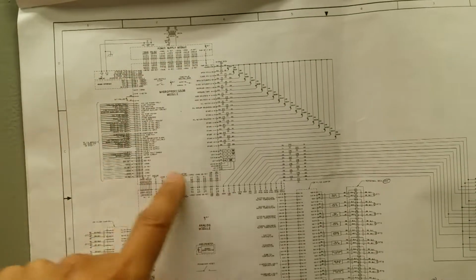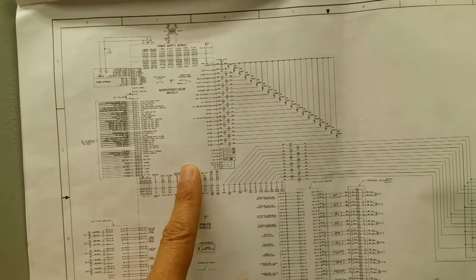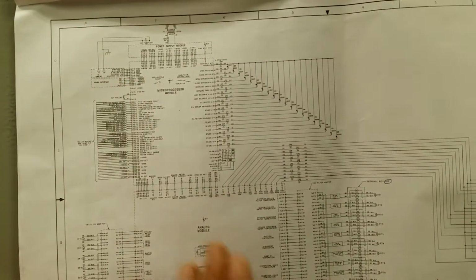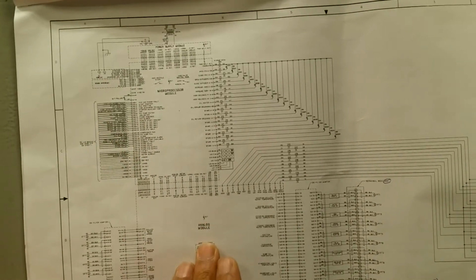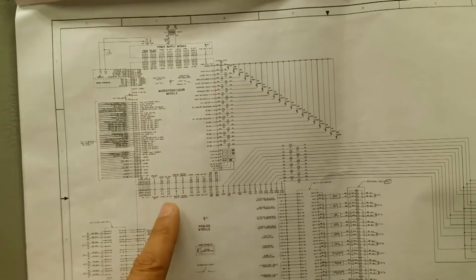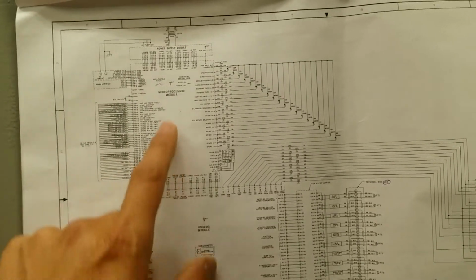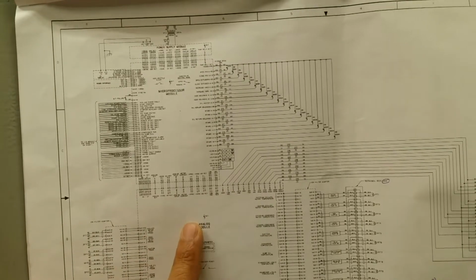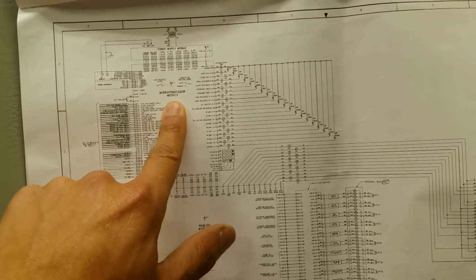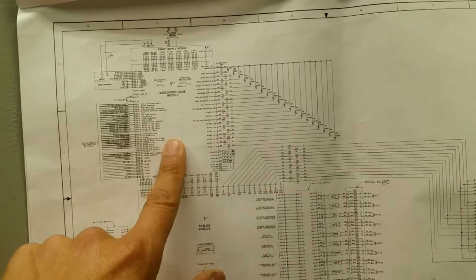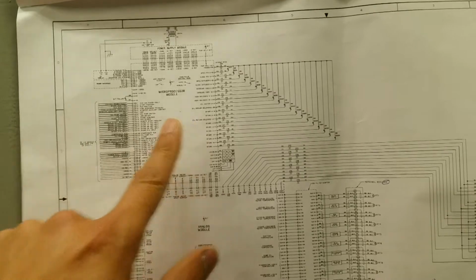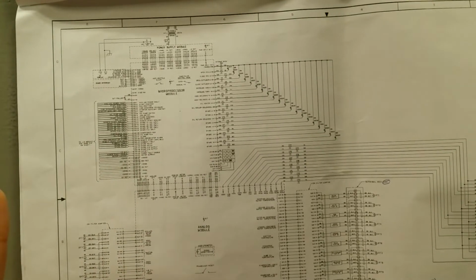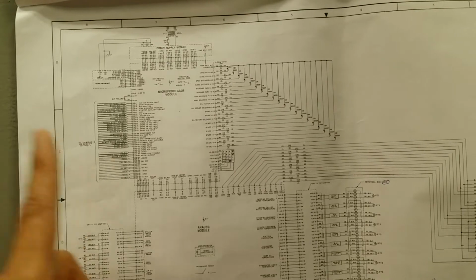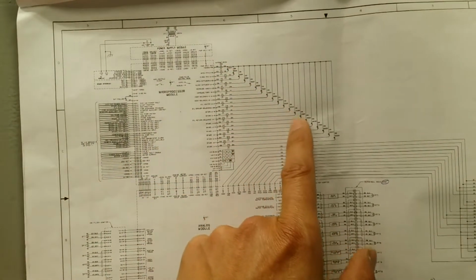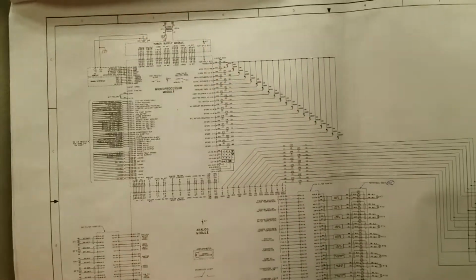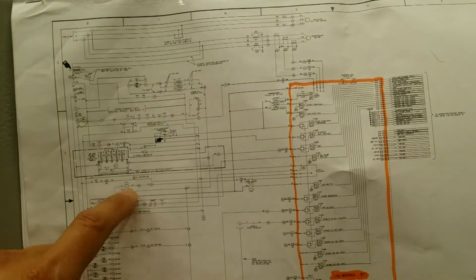The microprocessor module, as you can see over here, receives all the inputs from either the input module or the analog module. The analog module has 1 channel, which means pretty much 1 wire, and it gets all the information that this circuit card over here collects. This one is the brains. It does all the decision making, and based on whatever it decides, it will tell the input and output module to start the AC, because remember, the input and output module is the one that can start the AC via K1, or it will energize any of these associated SSRs to open and close valves as it desires.